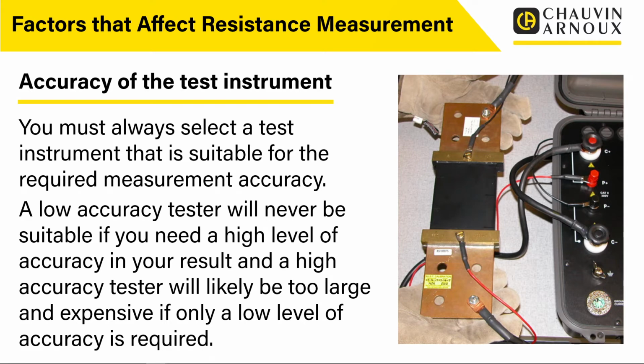They think, well, we need a massive level of accuracy, when actually all they're going to do is drive themselves up the wall, because they've got a huge great tester, it's really accurate, in which case it's really sensitive to temperature fluctuations and really sensitive to all sorts of test conditions. When actually, if all you wanted to do was measure to a reasonably low tolerance, you may have got away with a simple 2-pole tester, when really you've bought a 4-wire tester and you're driving yourself mad trying to get it to work in an on-site environment maybe.